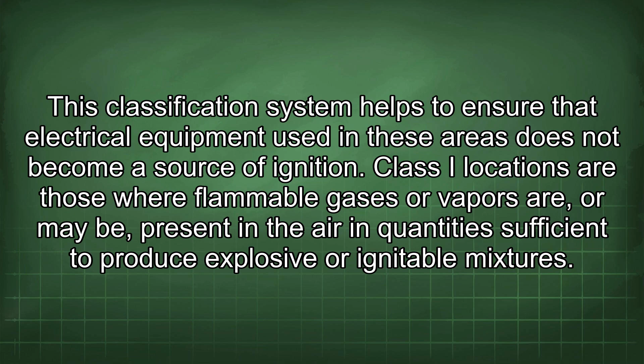Class I locations are those where flammable gases or vapors are, or may be, present in the air in quantities sufficient to produce explosive or ignitable mixtures. Examples include petroleum refineries, gasoline storage areas, and spray finishing areas where volatile flammable solvents are used. Class II locations are those where combustible dust is, or may be, present in the air in quantities sufficient to produce explosive or ignitable mixtures. Examples include grain elevators, flour mills, coal preparation plants, and areas where metal dusts are produced or handled.